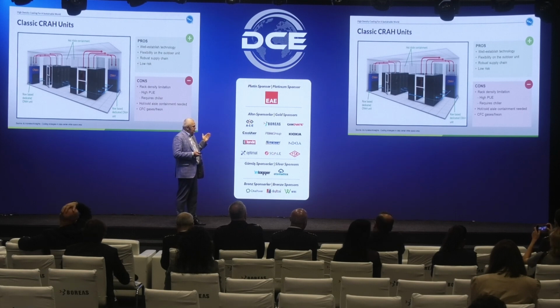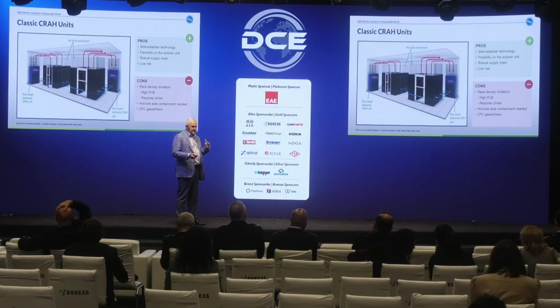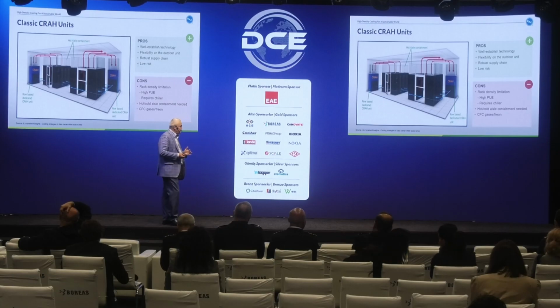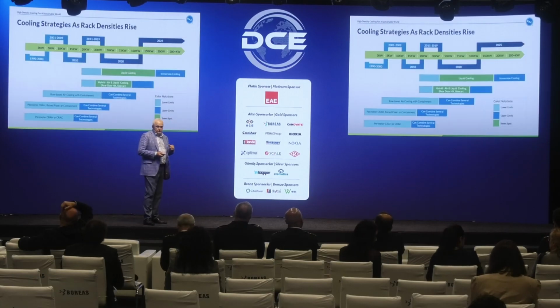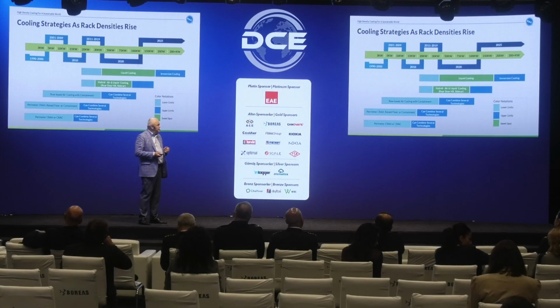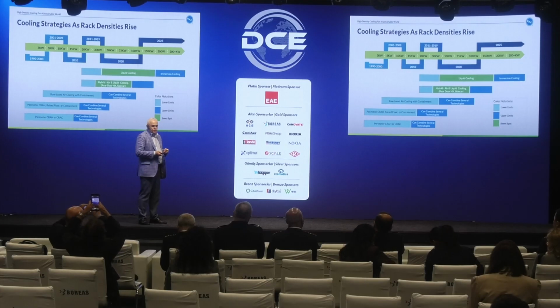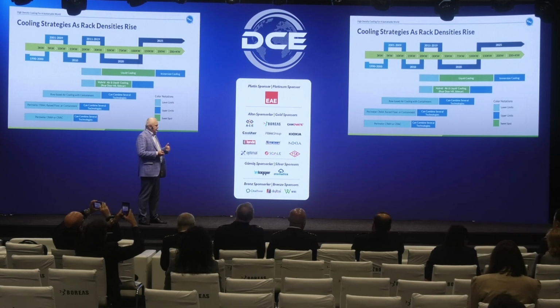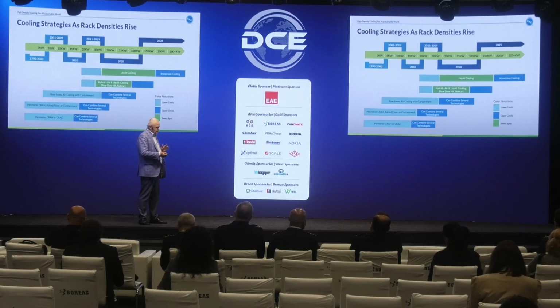And as I said, after that there was a new evolution. They installed hot aisle, cold aisle containment to segregate the supply and return and to increase the delta T. This is the evolution of the density inside the data center. Basically, it started at 3 kilowatts per rack using computer room air handling units and computer room air conditioning units. After they reached the limit, they introduced the containment, hot aisle, cold aisle containment, and the perimeter in-row coolers. Next step, together with the containment, they started to have in-row coolers.